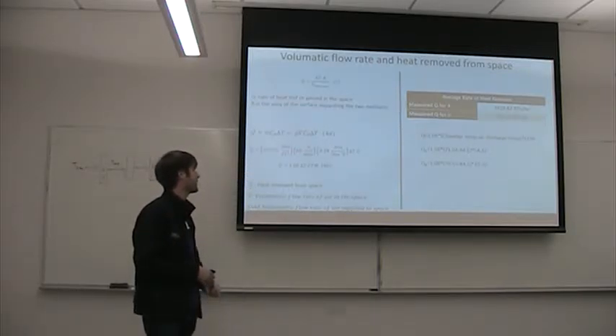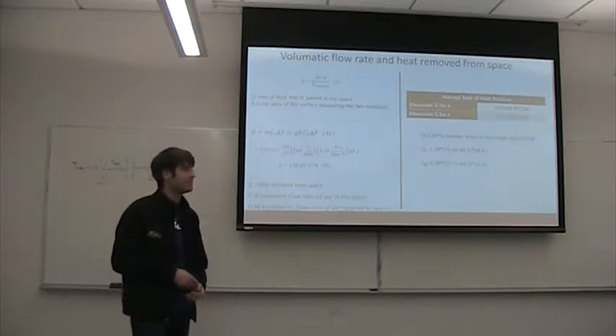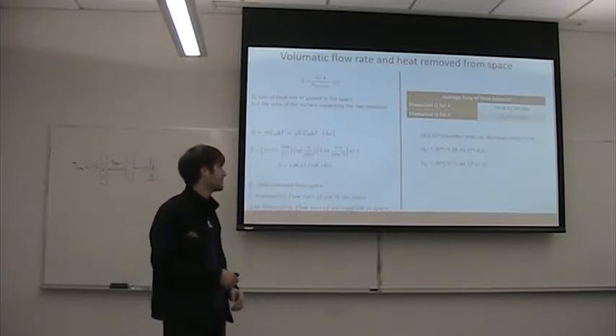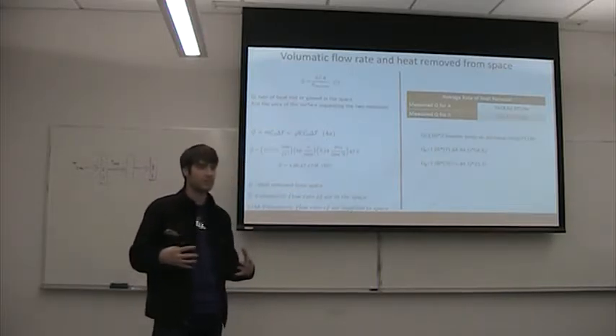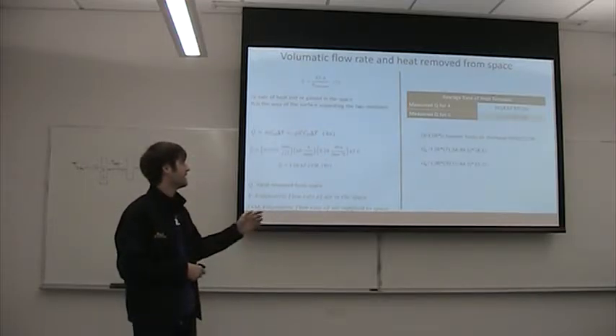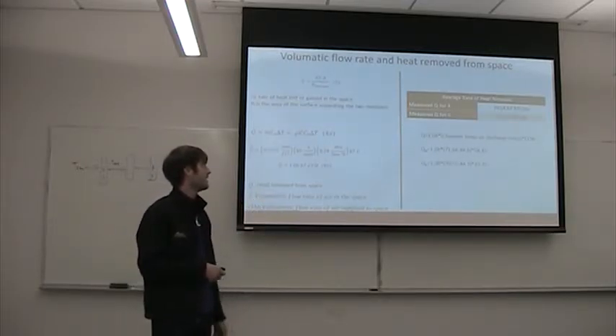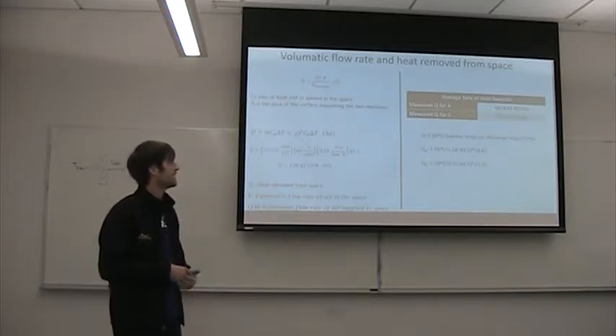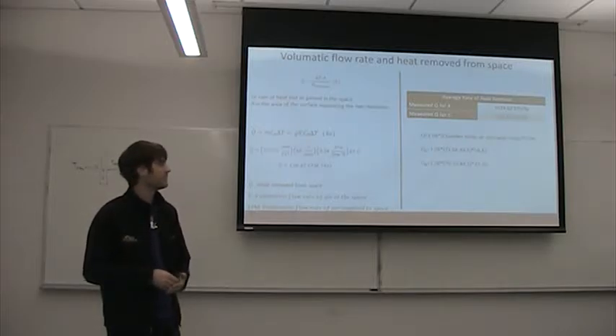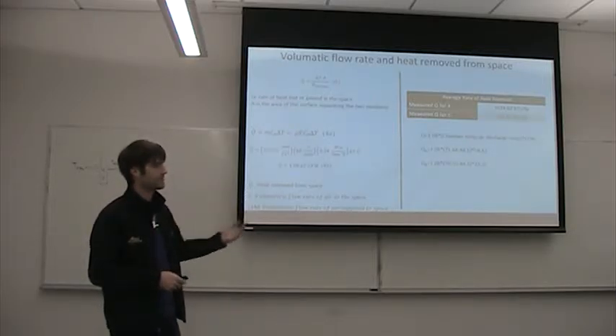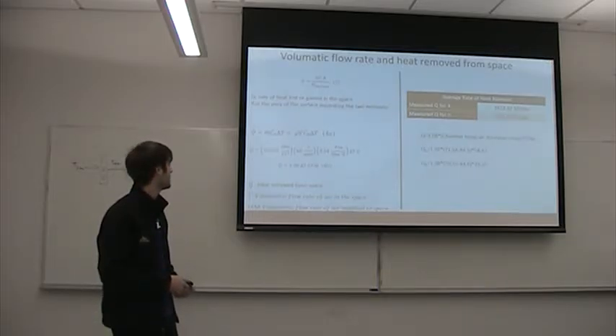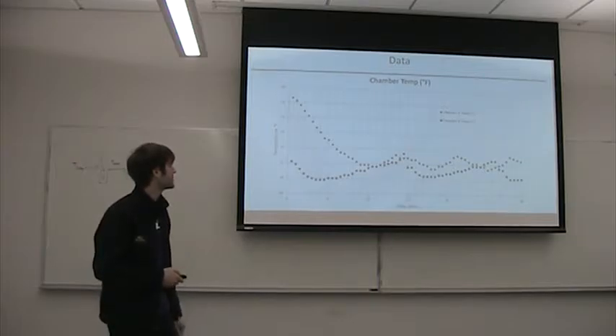So we went in to calculate the flow rate and heat removed from the space of the room. So you have this equation as heat removed as delta T times your area over R thermal. When you go in and you can move it into the simplified a little bit here, you get this equation as q equals 1.08 times delta T times your CFM.